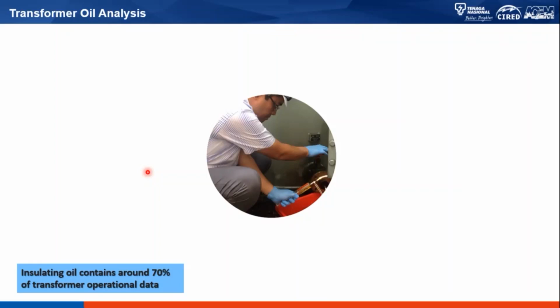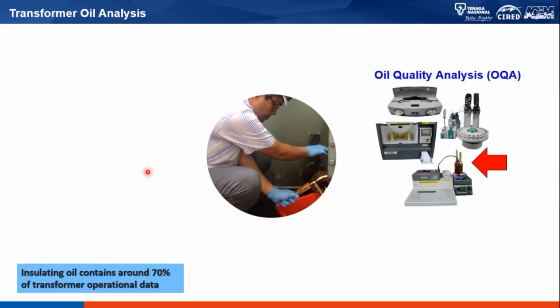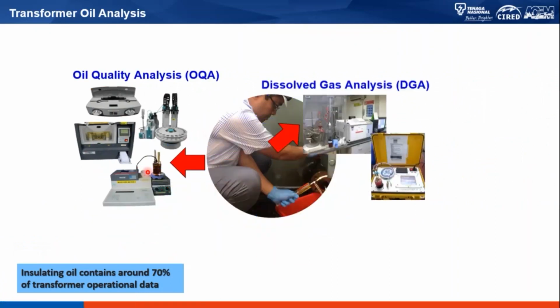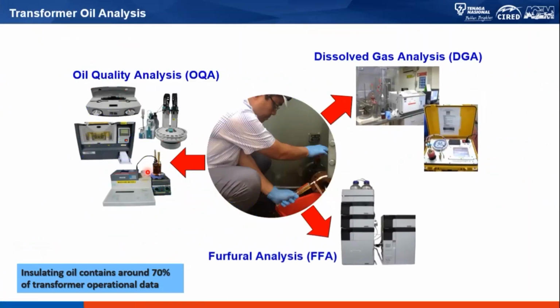And this mineral oil that we have inside our transformer acts as a medium that can provide us with a lot of information. Based on the literature, it is said that the insulating oil contains around 70% of overall transformer operational data. So if we want to know the condition of a transformer, it is best to take samples of the oil. When we take samples of the oil, what can we do with these samples? There are, of course, three kinds of analysis that we can do.